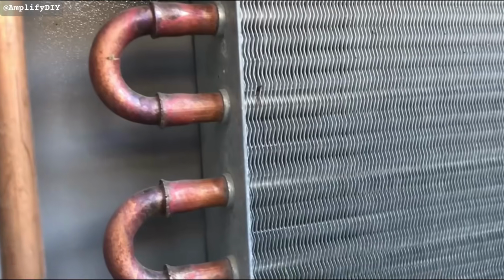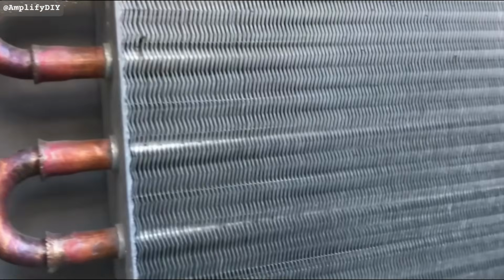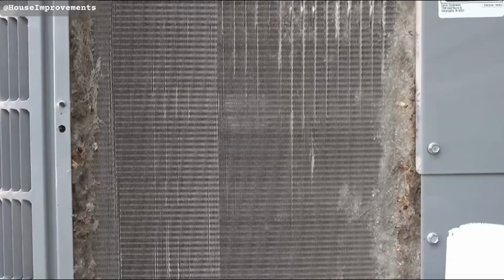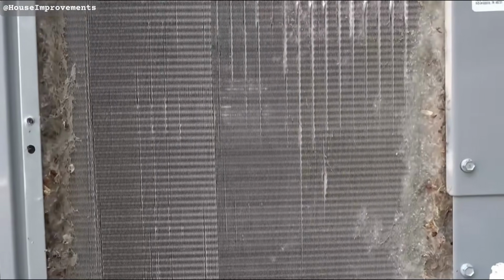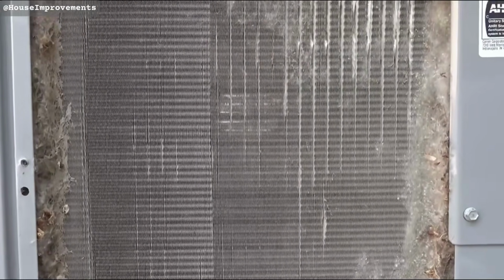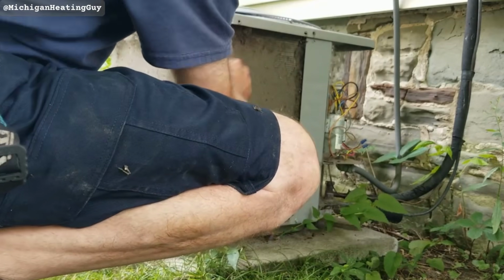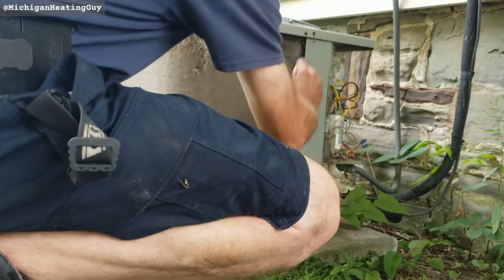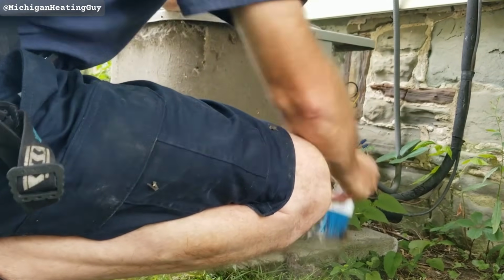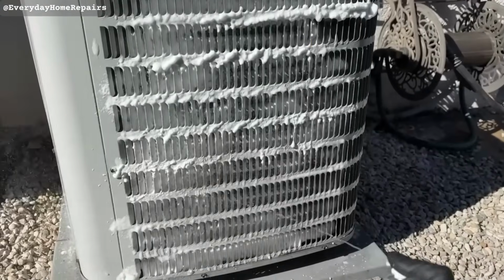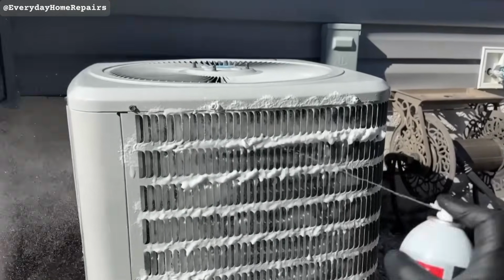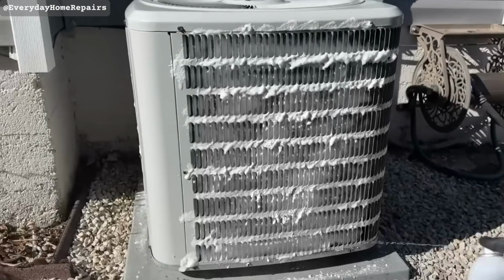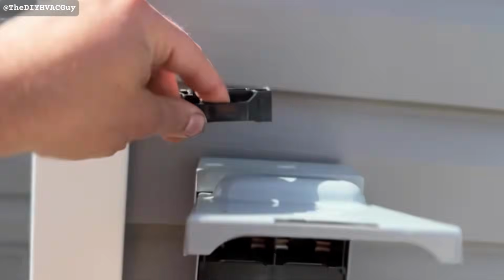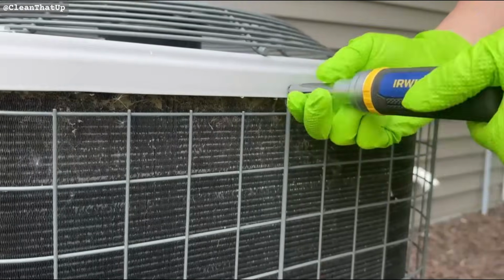A healthy residential air conditioning system, properly sized, properly charged, with clean coils and good airflow, produces a temperature drop of 16 to 22 degrees Fahrenheit between the return air and the supply air. Return air comes back to the system warm from the house. Supply air leaves the system cool, after passing across the evaporator coil. The difference between those two temperatures is the temperature split, and it tells you whether the cooling is actually happening at the rate it should.